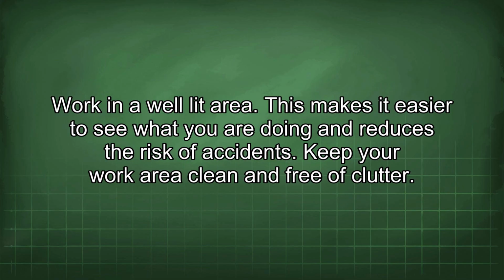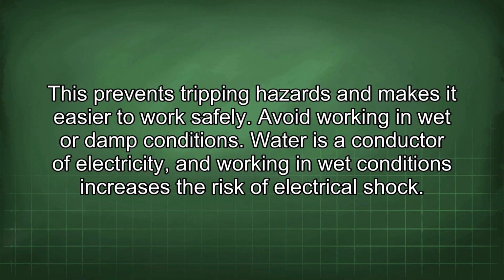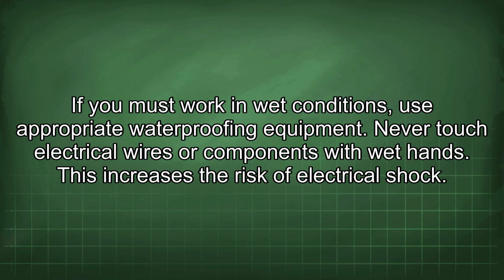Work in a well-lit area. This makes it easier to see what you are doing and reduces the risk of accidents. Keep your work area clean and free of clutter. This prevents tripping hazards and makes it easier to work safely. Avoid working in wet or damp conditions. Water is a conductor of electricity, and working in wet conditions increases the risk of electrical shock. If you must work in wet conditions, use appropriate waterproofing equipment. Never touch electrical wires or components with wet hands. This increases the risk of electrical shock.